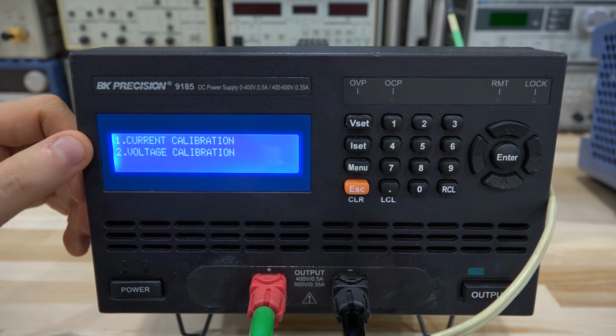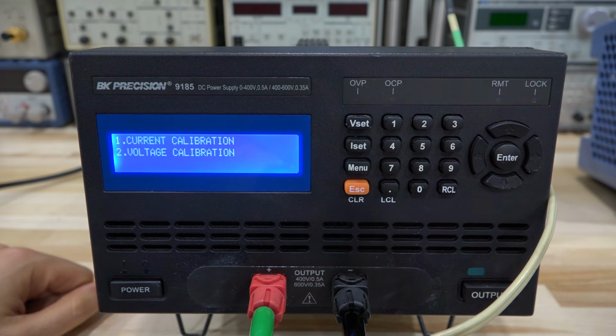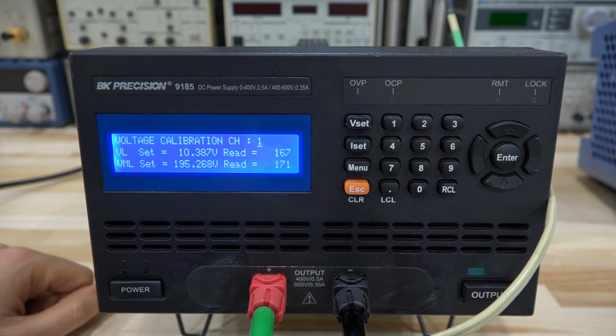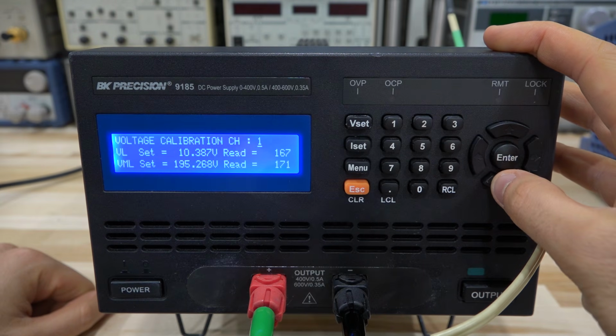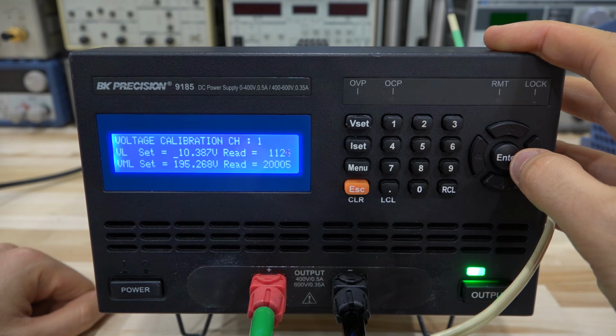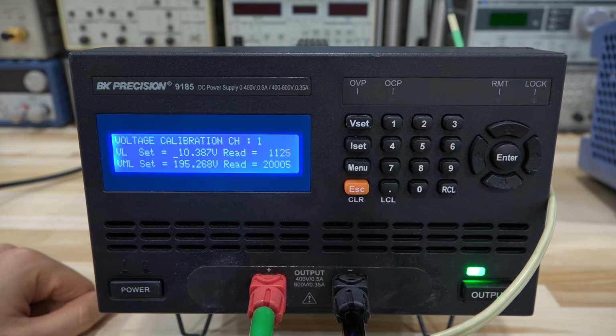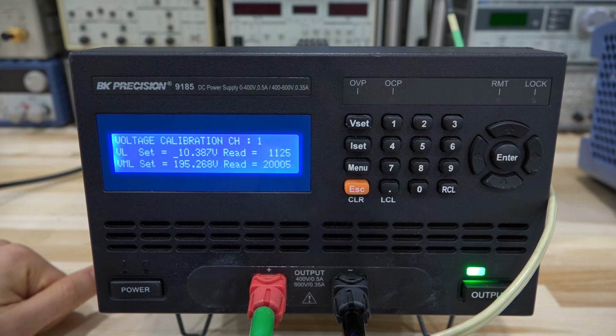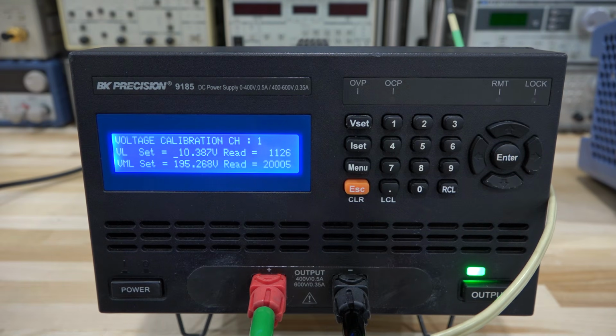So we can get current calibration and voltage calibration. We're setting voltage, so let's do a voltage calibration. And it says voltage calibration on channel 1. Yeah, this only has one channel anyway. Voltage set 10, and then the reading has to be adjusted. Voltage set 195, and the reading is adjusted. Okay, so what exactly do I do here? There it is. So yes, it is setting 10.387, and I'm reading 10.38. So I guess I'm going to have to adjust that. I'm not sure what that number is. I guess I should read the manual a little bit more carefully.